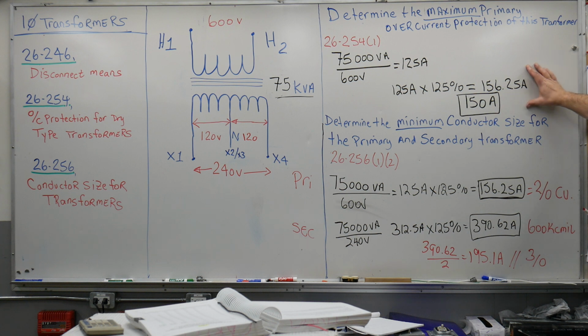Our maximum overcurrent protection is 150. The minimum conductor size is 2/0 copper on the primary. The secondary would be a single conductor 600 kcmil if it was one conductor. However, if you decided to parallel it, it's parallel runs of 3/0. 3/0 is much easier to deal with than this nasty little guy.